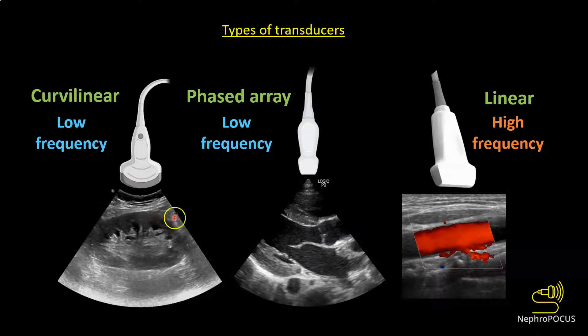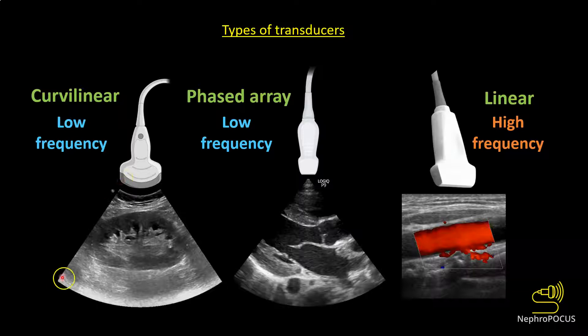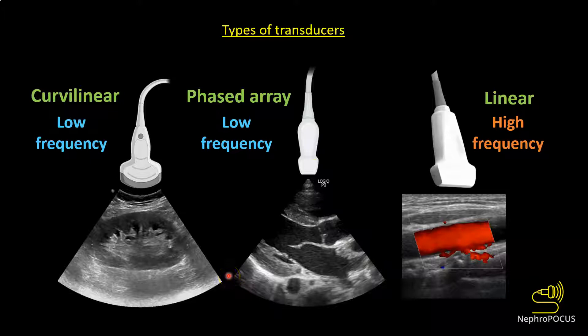Just by looking at how the ultrasound image appears, we can tell what transducer was used. In a curvilinear transducer, the piezoelectric crystals are arranged in a C-shape and the image appears like a fan covering a wider area. With the cardiac probe, the crystals are arranged at the center and the beam emerges from one point, giving a pie or pizza-slice appearance — facilitating movement between rib interspaces. In the linear probe, crystals are arranged linearly, producing a more rectangular image.